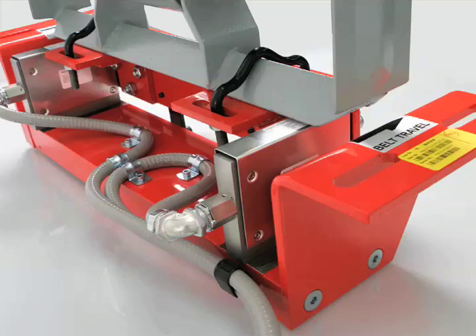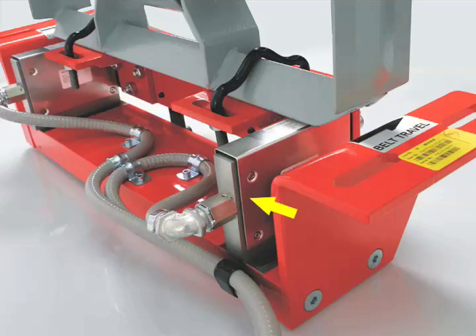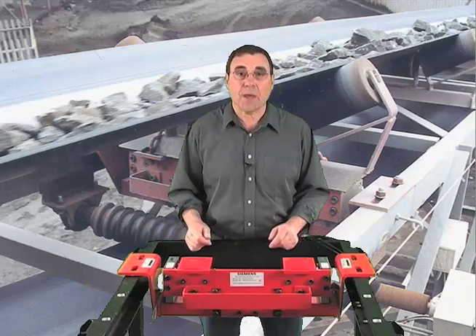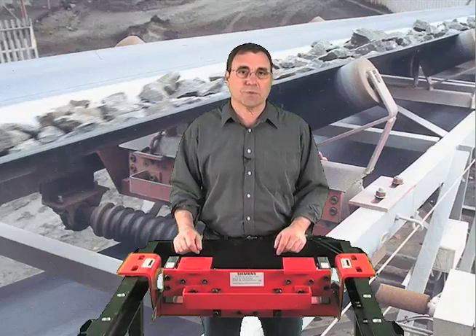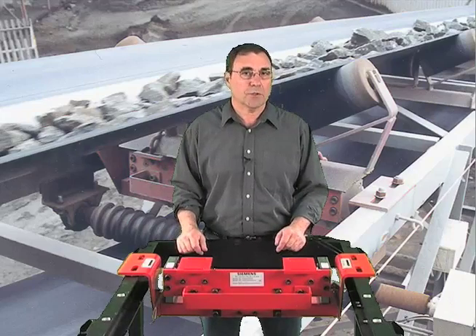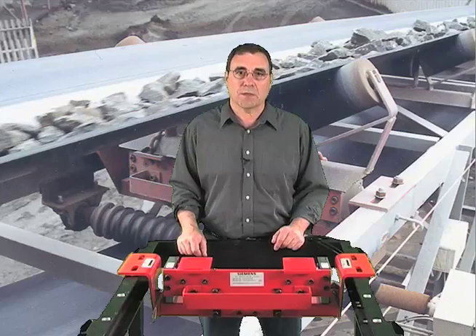The second consideration is durability. Our load cell is designed to last. It incorporates a built-in mechanical stop and static overload capabilities of 300 percent. We use a special sealing process to ensure the electronic strain gauges are protected from moisture and external elements. The suspension itself is compact and robust with few exposed components, making the Milltronics MSI really durable, providing you with years of uninterrupted service even in the most demanding conditions.